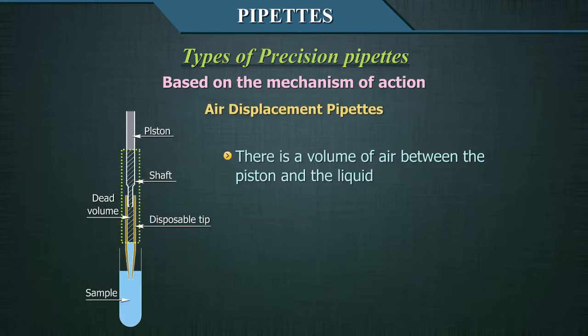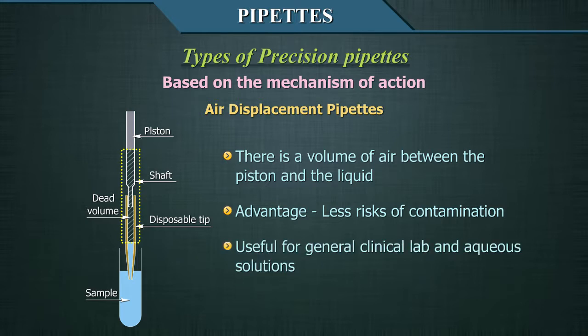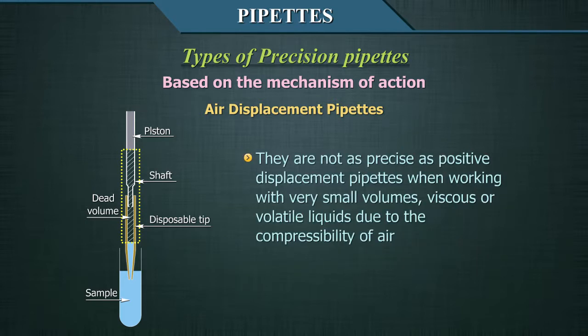In air displacement pipettes, there is a volume of air between the piston and the liquid. Air displacement pipettes have the advantage of presenting less risk of contamination and are useful for general clinical lab use and aqueous solutions. However, they are not as precise as positive displacement pipettes when working with very small volumes, viscous, or volatile liquids due to the compressibility of air.